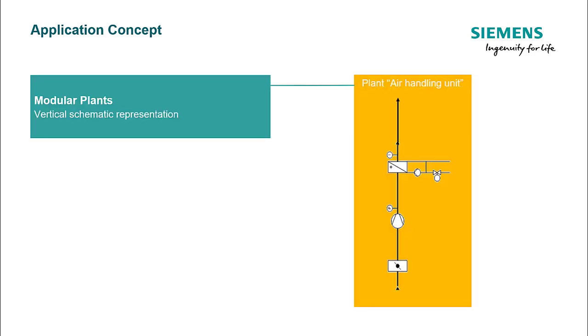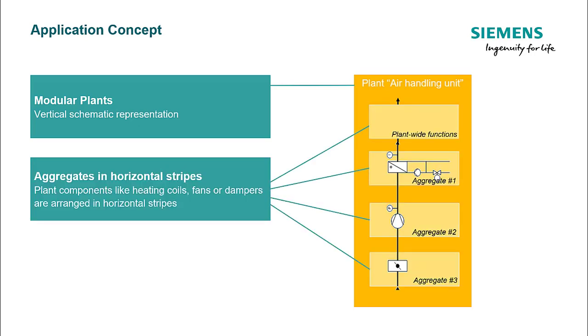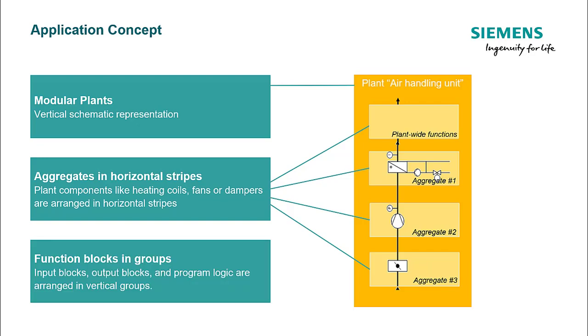Now we can go into more detail to find out how these components are depicted in a plant. A plant is arranged so that the schematic representation is vertical, then divided into horizontal stripes. Each stripe depicts an aggregate such as heating coils, fans, or air dampers, and includes input blocks, output blocks, and program logic for that plant component. To make the overview simpler, the function blocks are arranged in vertical groups.